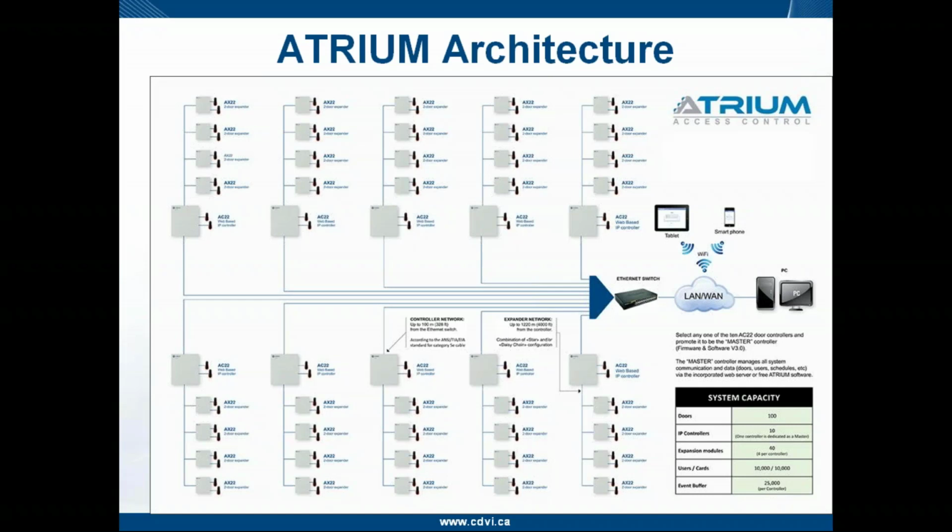Then we can add subcontrollers and so on and so forth. One of the things that I might put forward as a recommendation is your master controller will have multiple tasks to take care of. The default task by design is it controls 2 doors and it controls its own database internally on the board level itself. However, now we're asking it to do not only that, but we're asking it also to manage the master controller, to manage its subcontrollers, its door expanders, in addition to managing up to 49 subcontrollers.